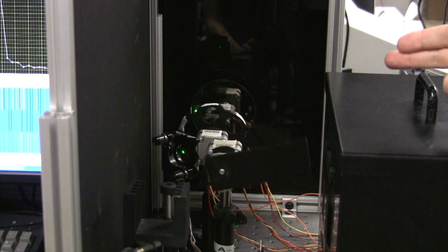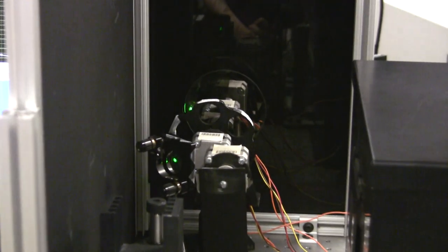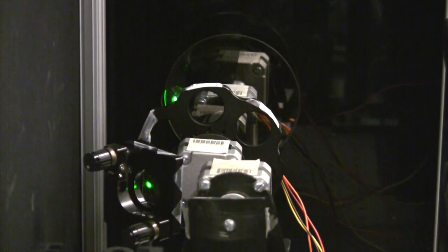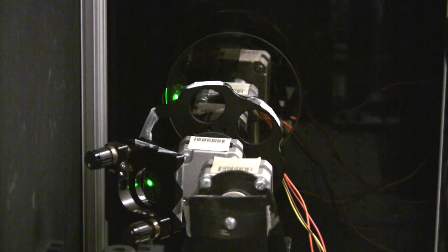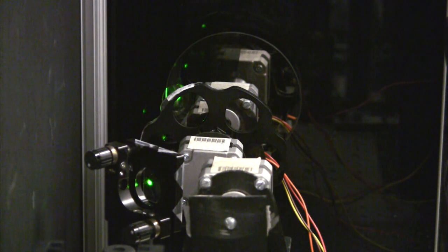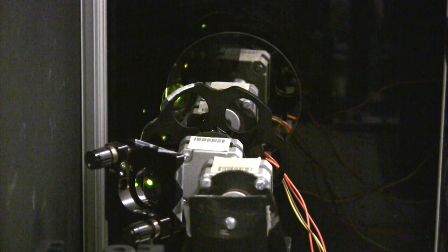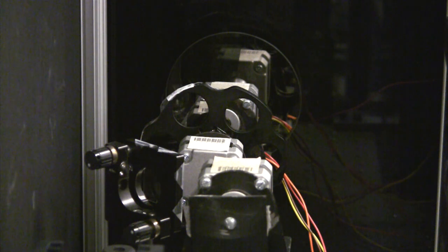When we start program first the shutter is being opened, and then the laser is going to be scanned from green towards red wavelengths. During this scan intensity of the laser light is being changed, and therefore sometimes we need to compensate for that, and that's why the filter wheel is turning to put in place some neutral density filter. And you can see that now we are already at some yellowish wavelengths, and pretty soon we will get to red. And we can go like that from pretty much green at 550 up to 1600 nanometers in the infrared.